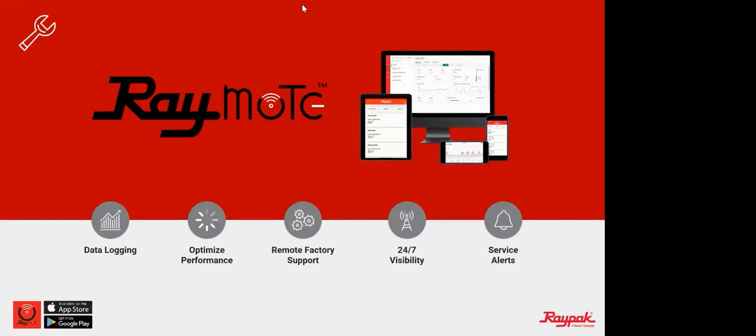And the other nice thing about Raymote is it will send you a notification if the boiler is locking out. You can set it up to send you an email or a text, or it'll just pop up as a notification on your iPhone. And what this does is allow us to get a little bit more visibility, and you guys. And the nice thing is, if you have a unit that is having some issues, if it's connected to Raymote, our tech support guys back in Oxnard are able to log into Raymote and find that boiler and see what's going on. And we're able to pull trends from the lockouts, data logging, all that stuff to maybe help dial in what's causing that problem.